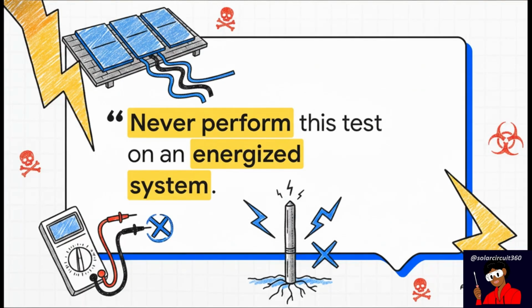Finally, let's wrap up with Section 5, True Protection versus Compliance. Okay, before we finish up, I need to aggressively highlight a crucial safety warning. Never, ever perform a Megger earth resistance test on an energized system. Period. You must always isolate your grounding electrode from the rest of your solar system before testing. If you leave the system connected while injecting current, you could completely destroy your expensive testing equipment, or much worse, expose yourself to a severe, potentially lethal shock. Safety first, guys. Always isolate the ground.